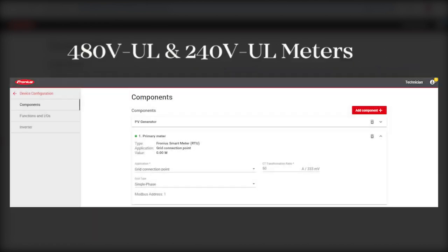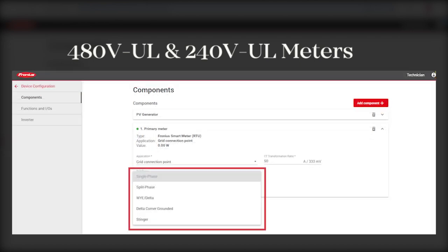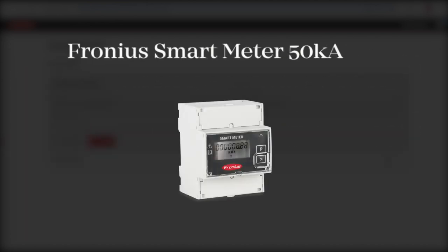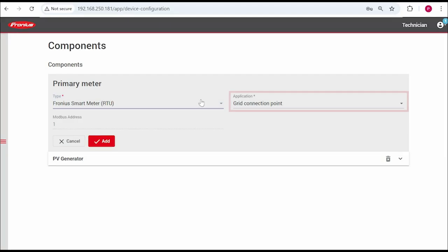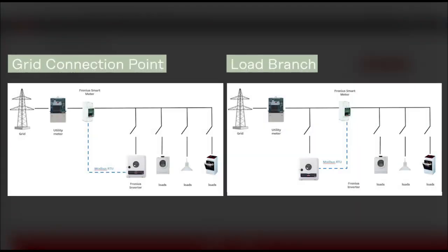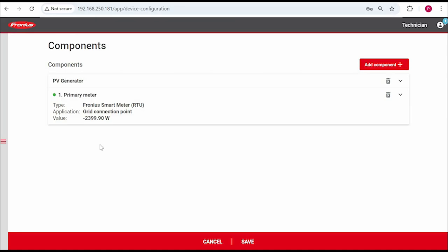The process is similar for the 480 volt UL meter or 240 volt UL meter, but just note that the grid type options are different. Also regarding the CT ratio, just note if you are installing a 50 kA smart meter, you'd enter in the CT ratio on the screen of the meter itself. The application section has two options depending on how you have wired up the site. Grid connection point is usually what you would select. This picture shows you the difference between grid connection point and load branch, which is the other option that you could select. Once you're done, click Save to apply the settings.